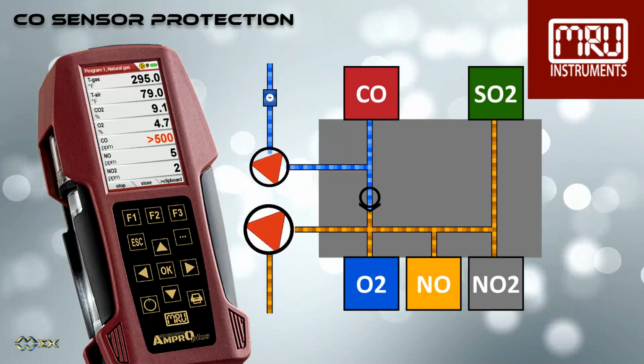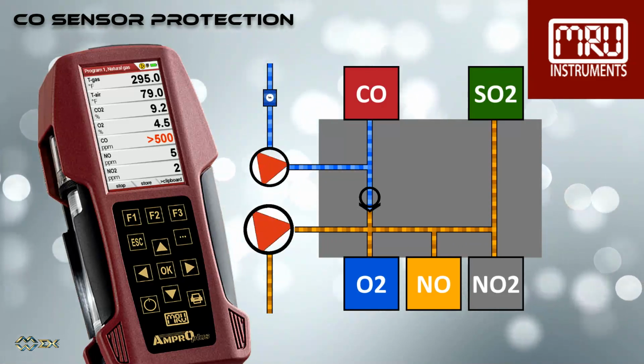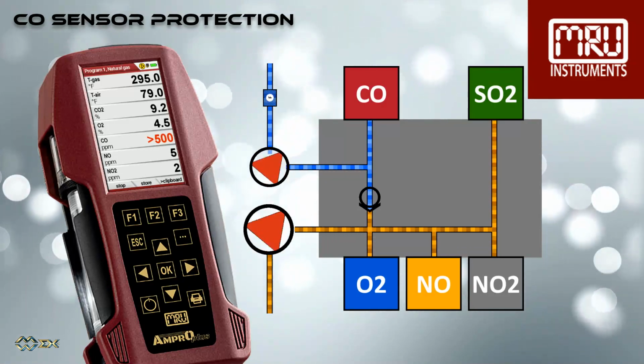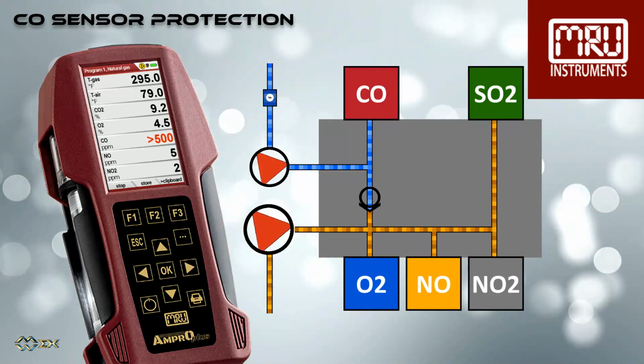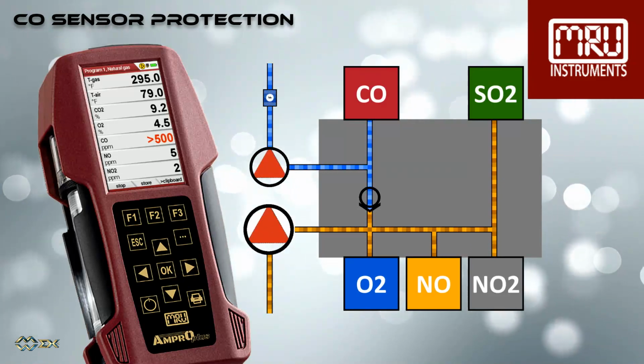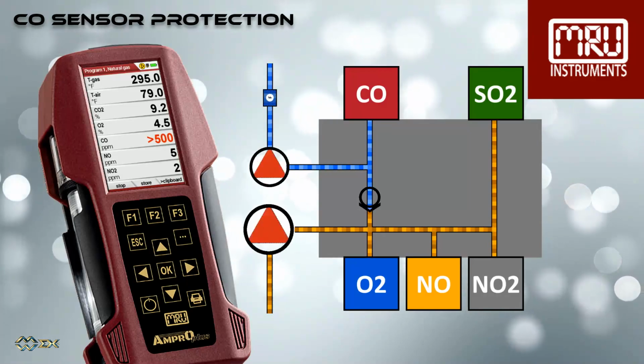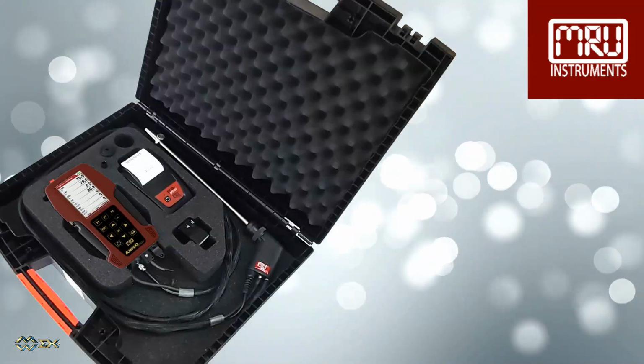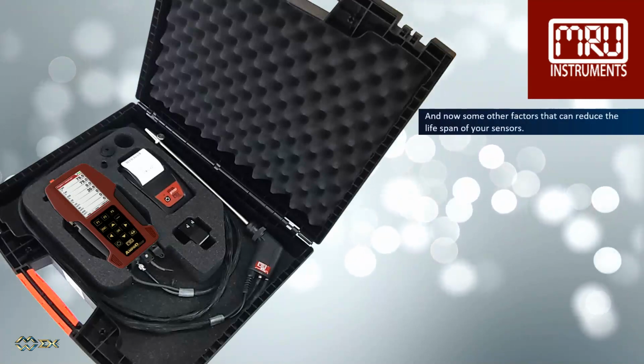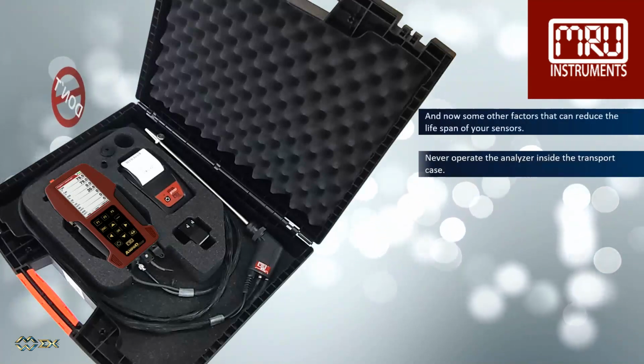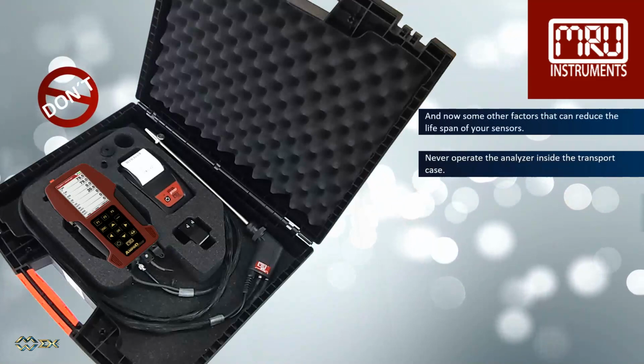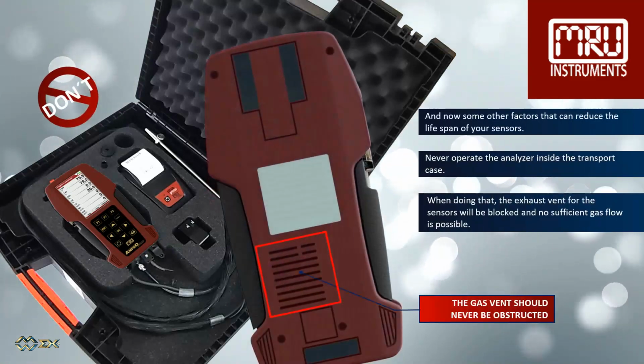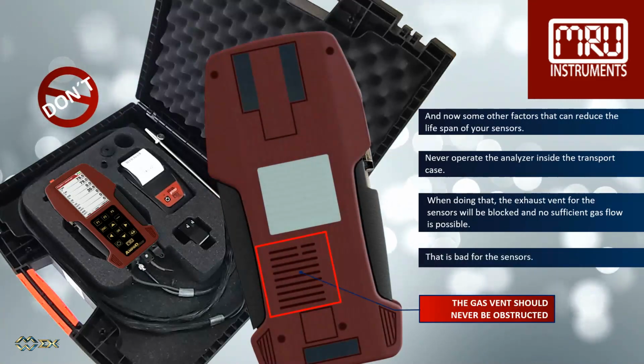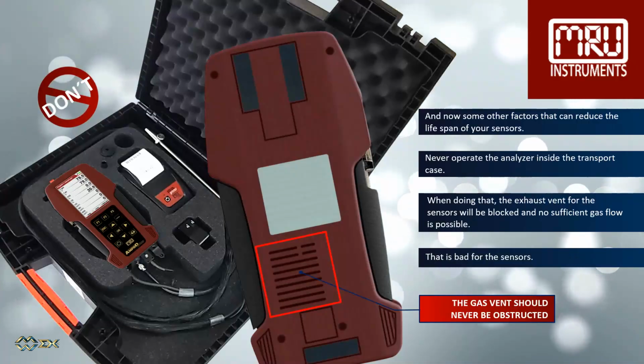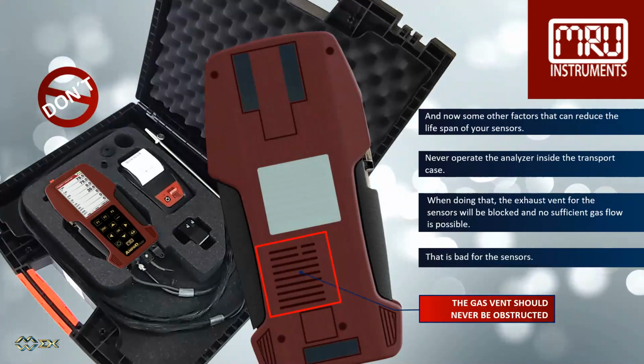All other sensors are not affected by the CO purge, oxygen, nitric oxide, and all other installed sensors will keep reading the undiluted gas. This CO sensor protection gives you peace of mind and will lengthen the lifespan of your CO sensor. And now some other factors that can reduce the lifespan of your sensors. Never operate the analyzer inside the transport case. When doing that, the exhaust vent for the sensors will be blocked and no sufficient gas flow is possible. That is bad for the sensors.